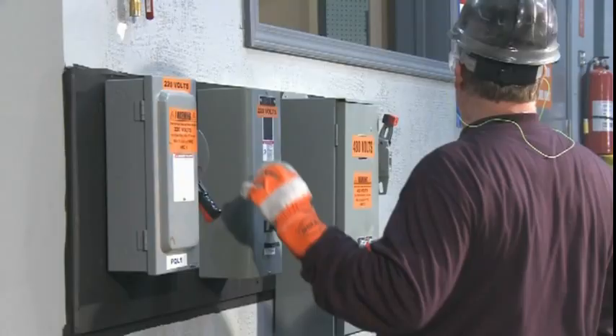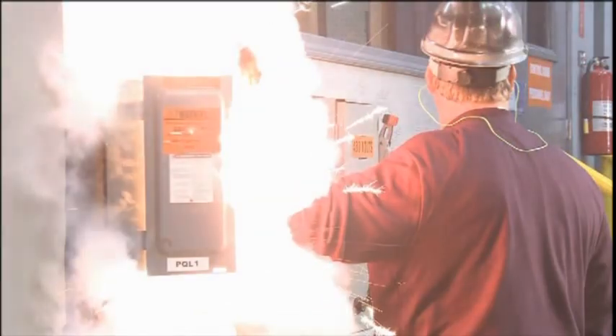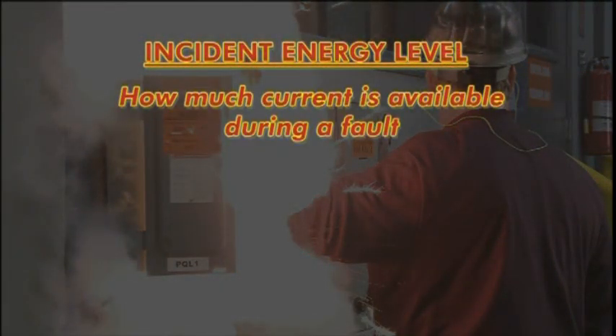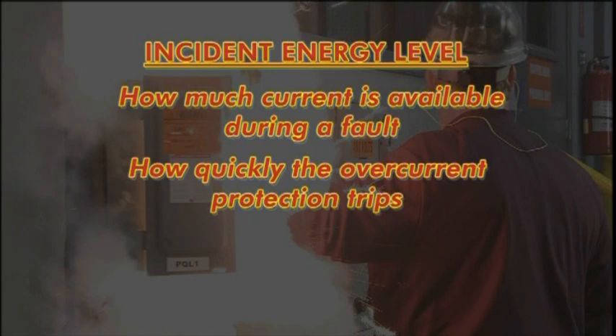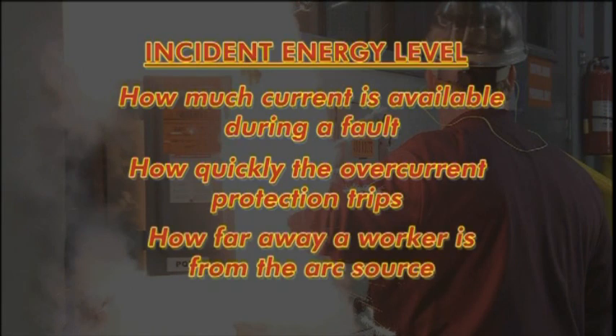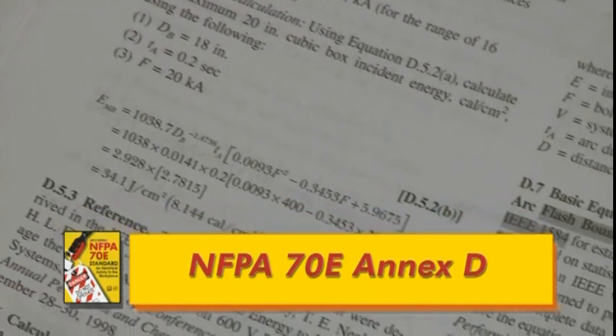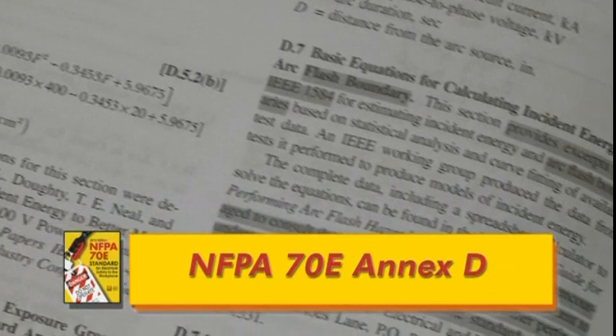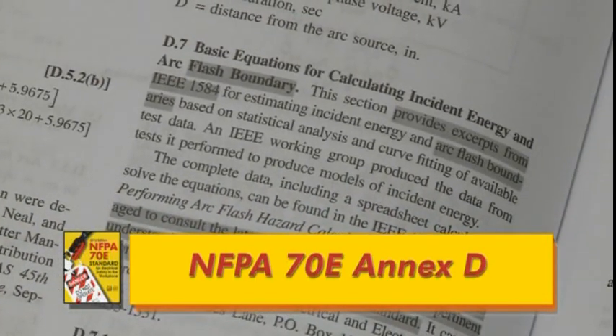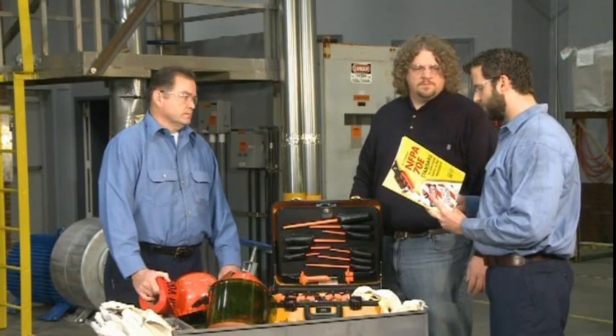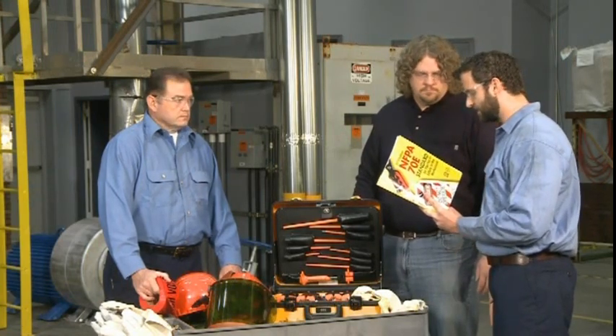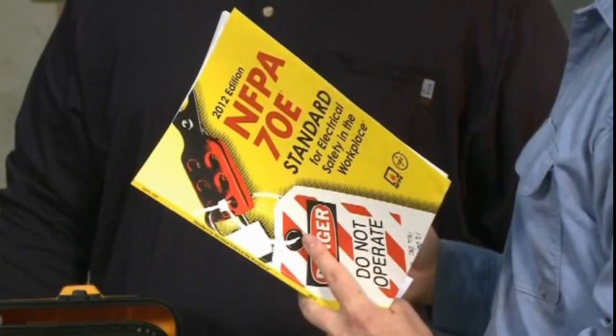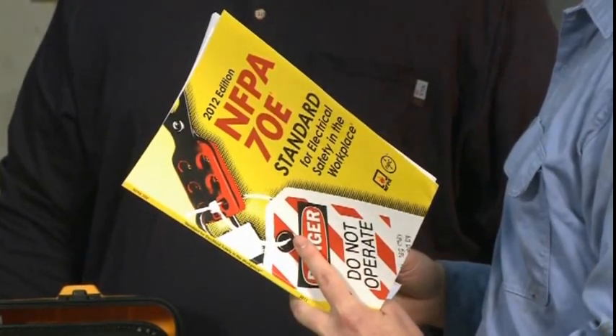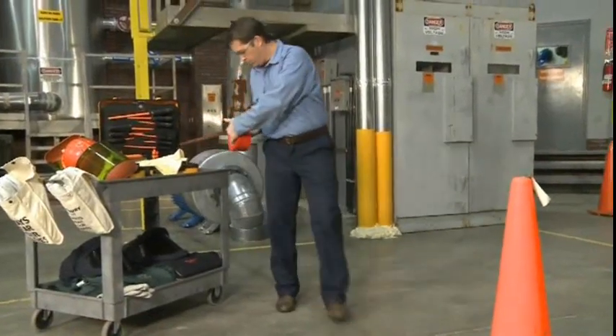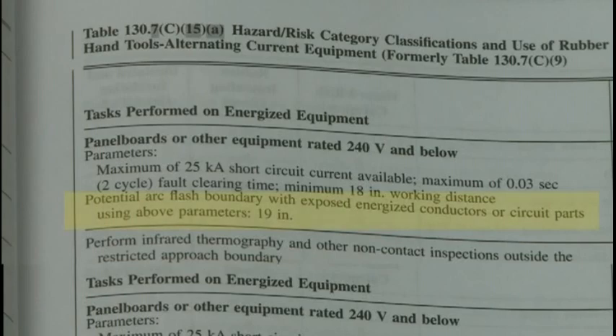The incident energy of an arc flash depends on how much current is available during a fault, how quickly the overcurrent protection can trip, shutting off that current, and how far away a worker is from the arc source. Various methods for calculating incident energy and the arc flash boundary are illustrated in NFPA 70E Annex D. To make it easier for workers to determine an appropriate arc flash boundary, the 2012 edition of the NFPA 70E has included an arc flash boundary for common types of electrical equipment and systems.